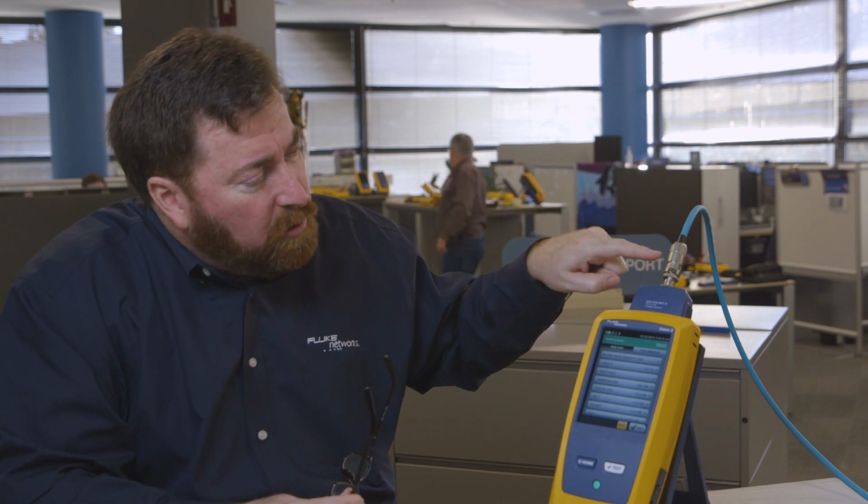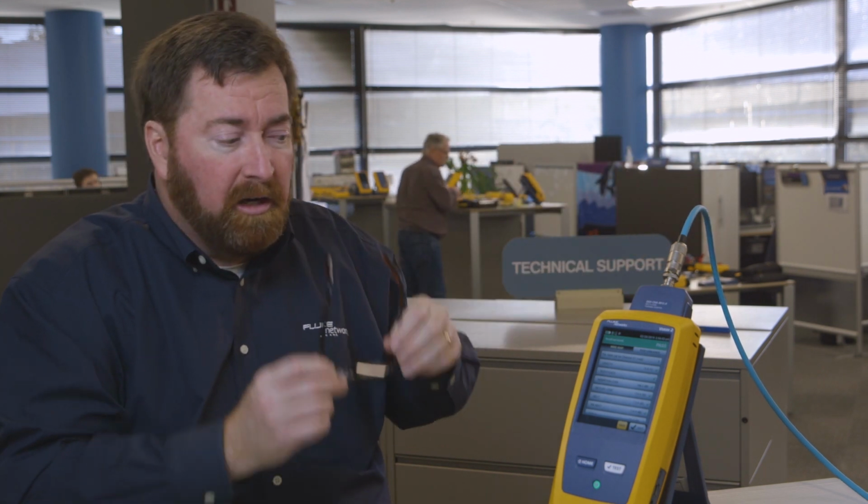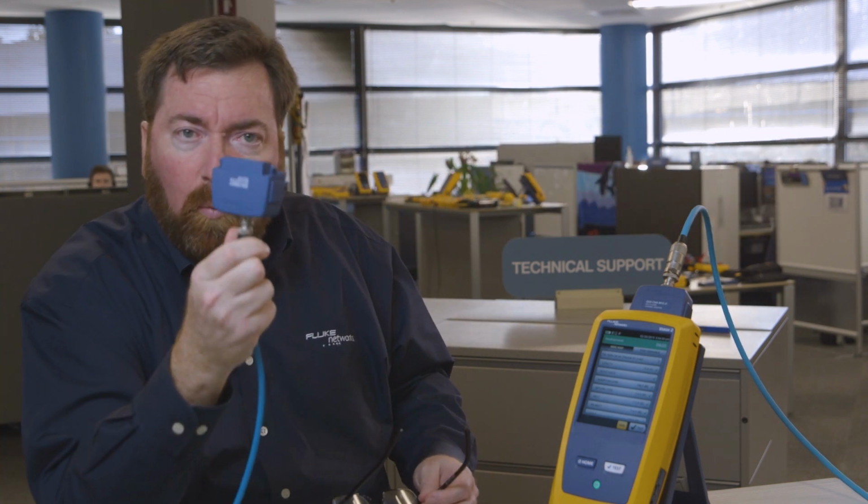This discrepancy in the standards is first being addressed by the ISO, the International Standards Organization. And in the ISO 11801-3, which are the cabling standards applied to an industrial environment, they have a new set of limits known as the end-to-end limits. The idea of the end-to-end limits is they will include the mated NEXT between this field-installed plug and our adapter. So, if we have a factory-installed plug, we can use channel limits. If we have a field-installed plug, we want to use the end-to-end limits.